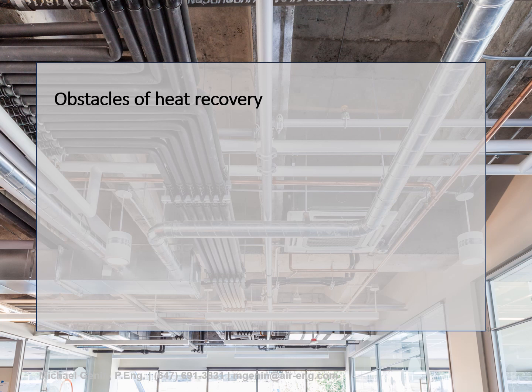So what are some of the obstacles of heat recovery, and why isn't it implemented as often as it should be? The first is you might have intermittent simultaneous loads. In order to do heat recovery, you need what is called a simultaneous load, heating and cooling happening at the same time, so we can exchange that energy between the heating and cooling load. So what do we do about loads that are intermittent? The other issue is that a lot of HVAC equipment available cannot develop the required temperature that can be useful for the application. A lot of buildings need up to 180-degree hot water supply in the middle of winter, and the technology might not be there to develop that amount of heat reliably, especially from cold sources.